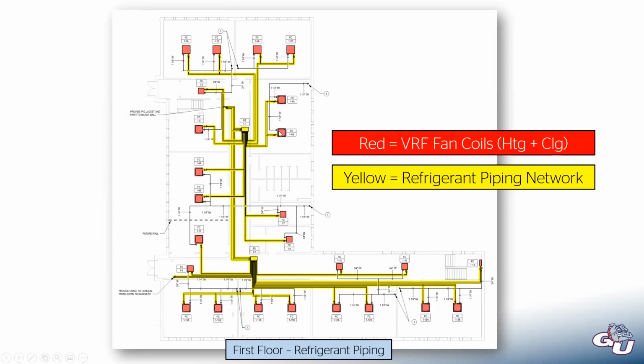What this network allows us to do is for all of these units to share energy. On a moderately cold day, but it's still very sunny out, on this south side down here, you could get the sun just beaming in through these windows that will tell these units we need air conditioning in this room, even if it's cold outside. Whereas these classrooms back here that don't have that problem might need heating. So this room would be rejecting heat into the refrigerant network, which can then be used by these spaces out here.